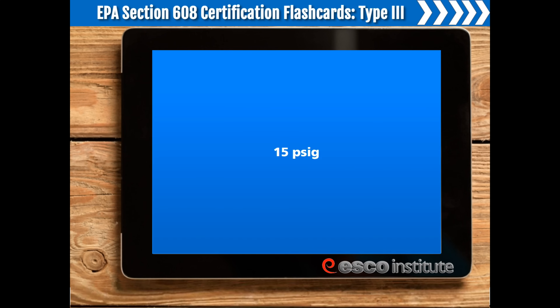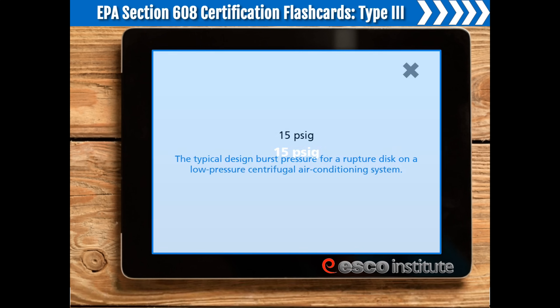15 PSIG is the typical design burst pressure for a rupture disc on a low-pressure centrifugal air conditioning system.